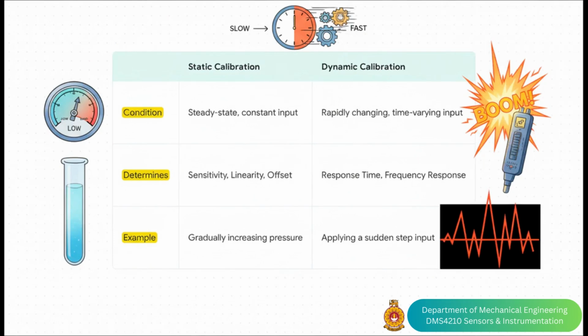Then there's another way to slice it: timing. Are you measuring something that's staying still or changing like crazy? Static calibration is when you test under steady, constant conditions, like slowly increasing the pressure on a sensor. Dynamic calibration is the opposite. It's all about testing how well a sensor can keep up with rapid changes, like a sudden spike in temperature.